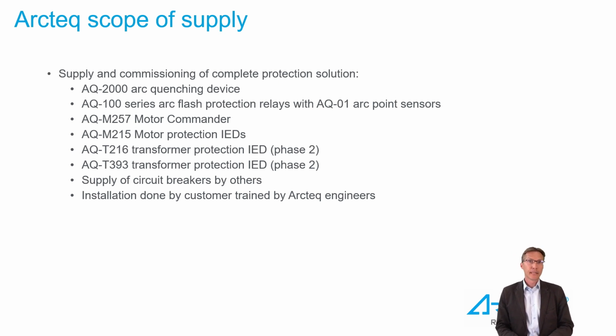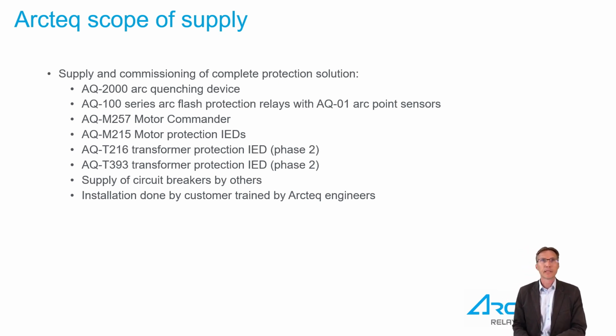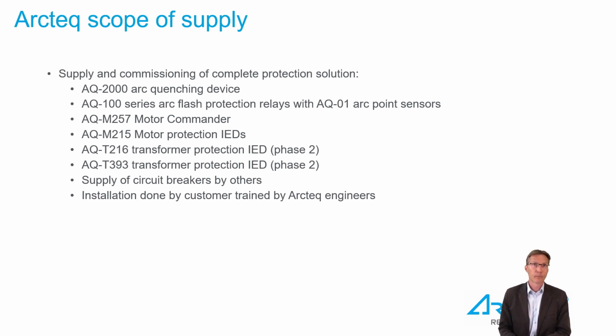Arcteq total scope of supply included in this case a kind of complete protection solution. So our scope had the quenching device and the AQ100 series arc flash protection relays, as shown in the previous slide. We included the motor commander already before the full retrofit activity, in the form of M215 motor protection IEDs, and the second phase of the project involved retrofitting of transformer protections, both 3-winding and 2-winding transformers. Circuit breakers were supplied by others, and the installation was carried out by the customer, who in turn was trained by Arcteq engineers. So our scope of supply was equipment, training, and commissioning of the system.